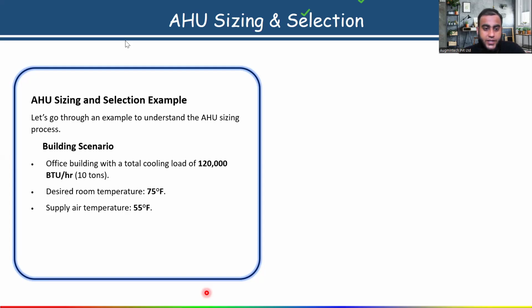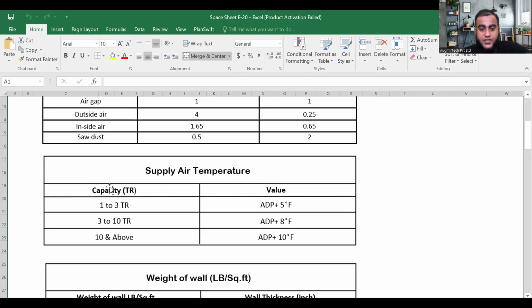Okay, so here I'm not getting that space sheet. In that, I have discussed everything. I think here it is given. See, all of you let me know, please, is my screen visible? To calculate the supply air CFM, see all of you, the table is given here. First, you have to know about the capacity. If you know the capacity, based on this capacity, you will get the supply air CFM value and supply air temperature value. See, first now you have to calculate the apparatus dew point temperature. Once you know the apparatus dew point temperature, based on capacity, these are the formulas which you have to use.